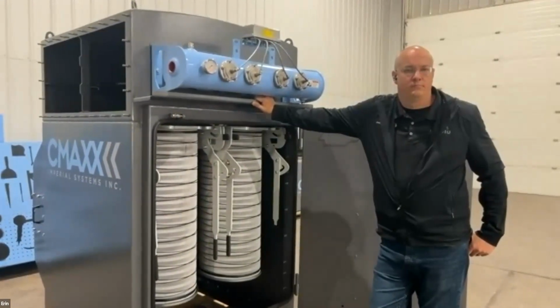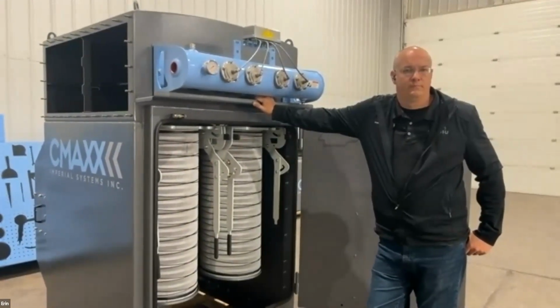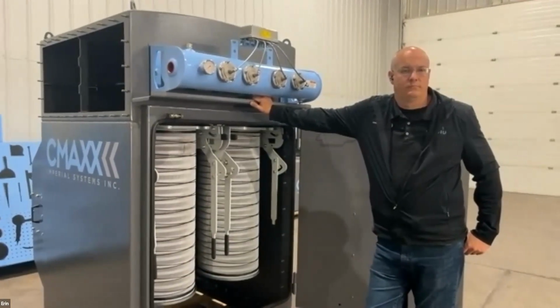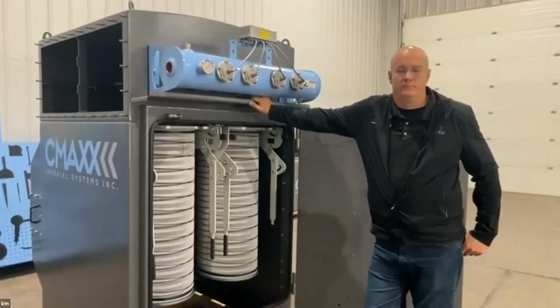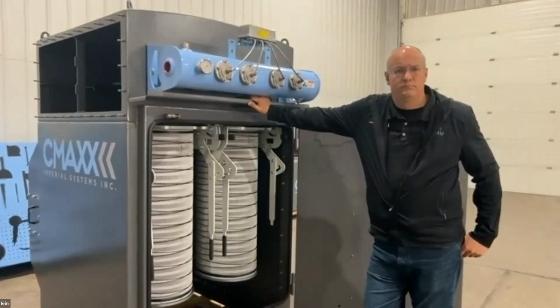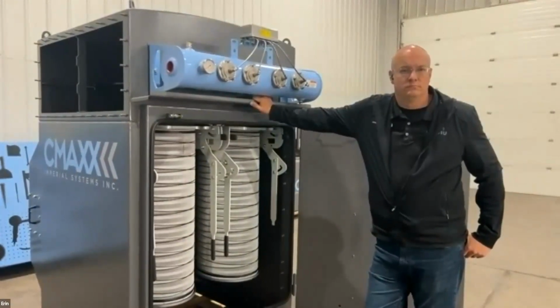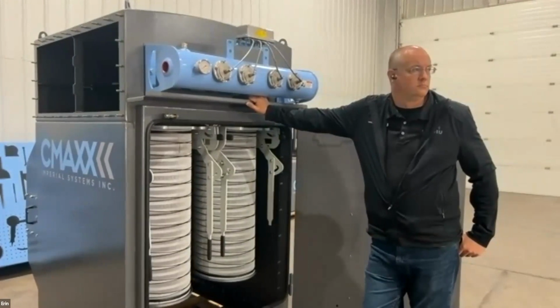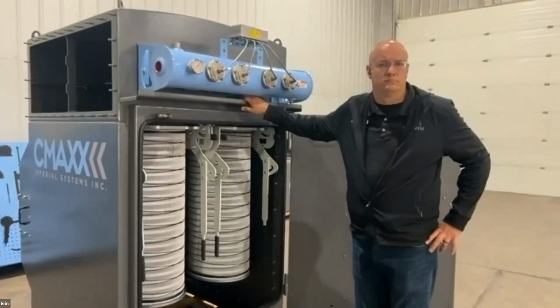It's gonna come out warm. And the key is when this air runs outside, you're gonna run 10 feet, 20 feet, however far away it is, might be sitting outside. You wanna make sure that that's as dry as you can get it going out there. So even though you've got piping through your facility, it's gonna leave your dryer in your compressor room dry.